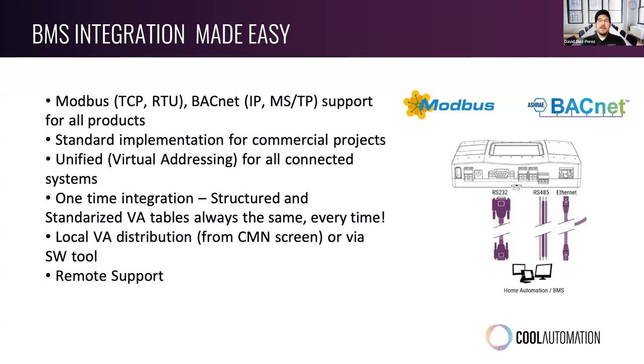We make that process so much simpler for you as a systems integrator. We carry the exact same unified virtual address table for all connected systems - it's a one-time integration. We keep structured Modbus registers and a structured list of BACnet objects for all your projects, no matter the brand, manufacturer, or number of units. We support BACnet and Modbus for all of these, both over RS-485 and over the local Ethernet network, making integration very simple.